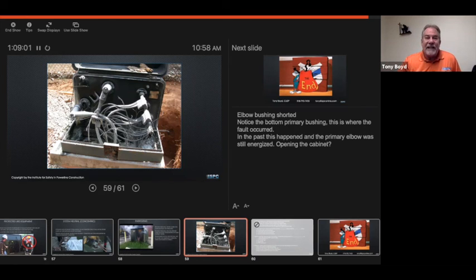I've also seen where transformers like this, all the secondaries are coming up and going in front of the primary conductors. And I've seen guys working on this part and actually make the elbow back off of the bushing. So just some things that we need to watch out for. Here's that vent. You would never pull this bayonet fuse out unless you vent it, because if you do, all that oil that's going to come in there comes shooting out. So that's the quick down and dirty.